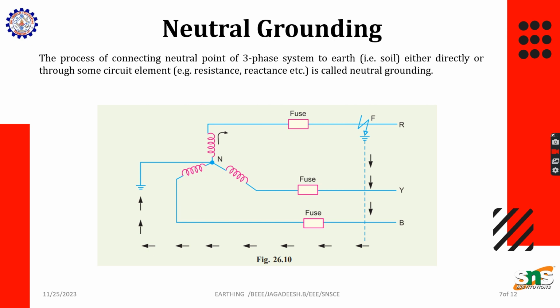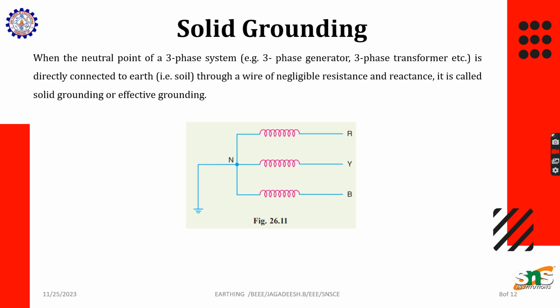Okay. And the third kind of grounding is neutral grounding. In a supply or in a machine, we may give input like three phases, R, Y, B, and the neutral point has to be grounded. This can be grounded directly to the soil through any kind of grounding to protect the machine from electrical shock. Let me take you through the different types of neutral grounding. The first one is solid grounding. When the neutral is directly connected to the ground, it is called solid grounding. No intermediate equipment or system is used for the grounding.